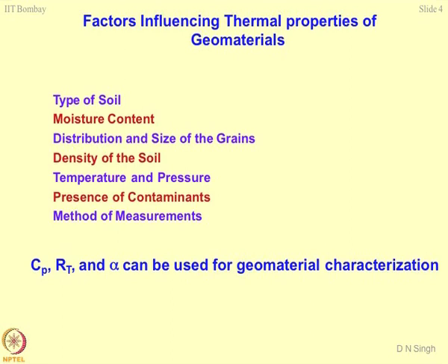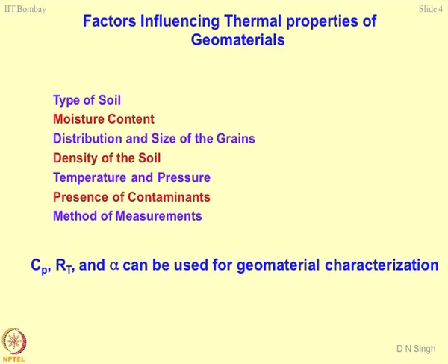Now, why is it important to study the resistivity of the soils? If you bury a cable which is conveying certain amperage, meaning a certain amount of current is getting passed through this cable, and if resistivity happens to be very high, what's your imagination? What is going to happen to the cable? Think of a situation where the temperature rises too much because of passage of the current. So, what will happen? The cable itself may melt, and once the cable melts, you can't convey any current from one point to another point. So, this is a situation where you require a system which dissipates heat, which is getting generated, into the soil mass or the porous media very quickly. So, resistivity for a good deposit in which the cable trenches should be laid should be very, very less.